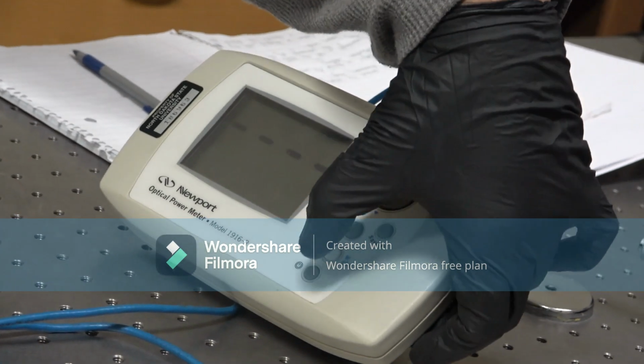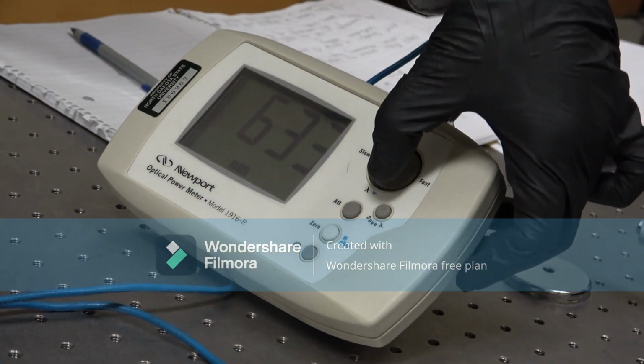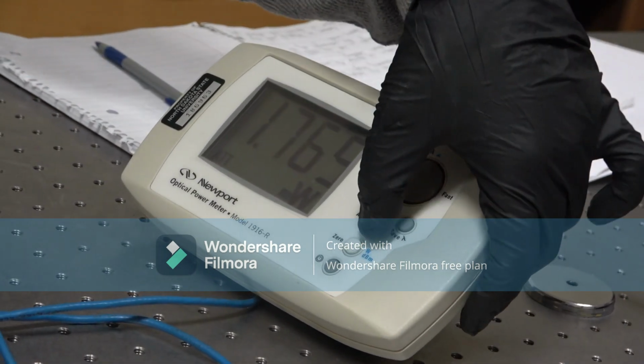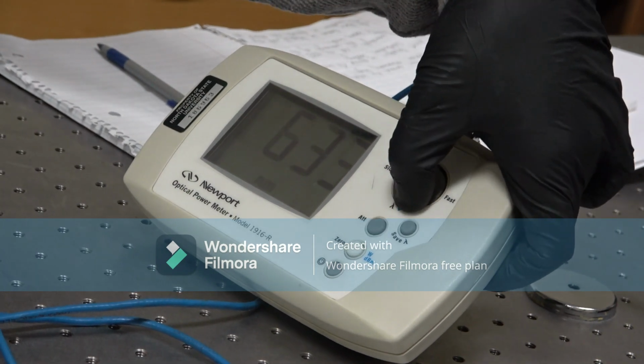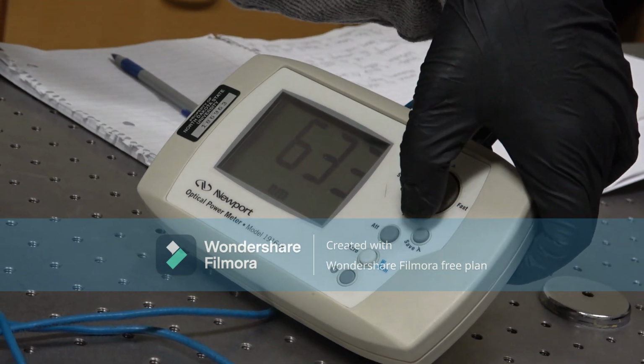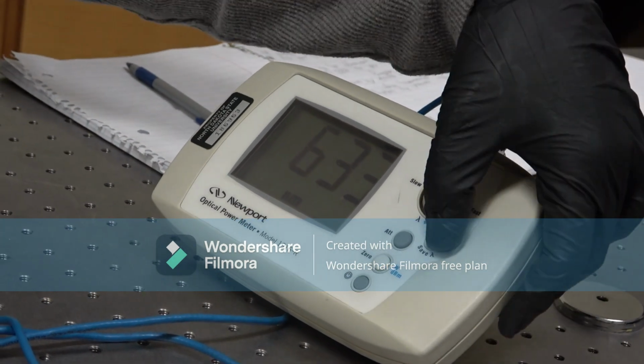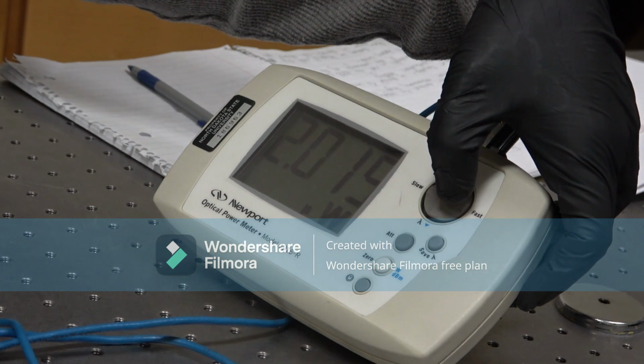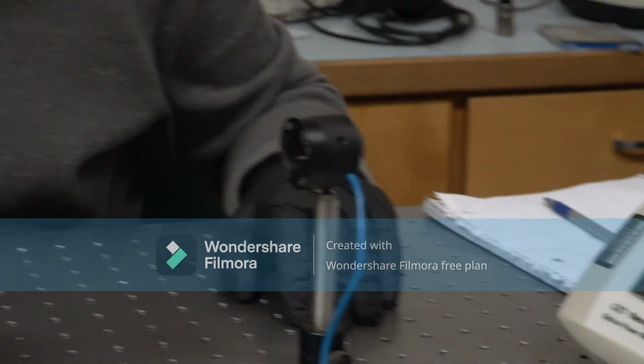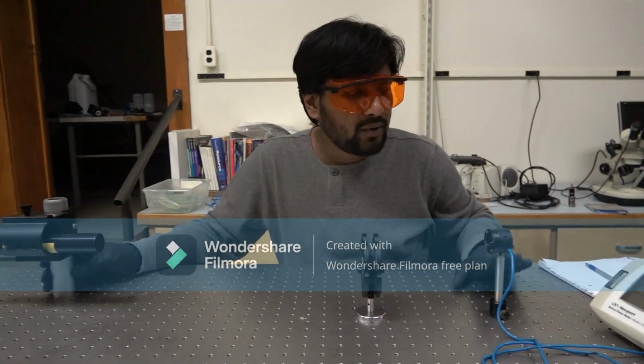Now let's start. First, we will turn on the power, and then we will press the ATT button, which will calibrate this OD3 filter. After that, we will press the lambda button, which is to calibrate the wavelength of this laser beam, which is set to 633. Now we will save this wavelength, and now it shows the power of this helium neon laser beam without any neutral density filter in place.